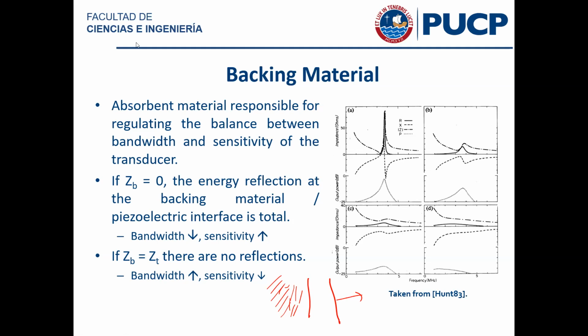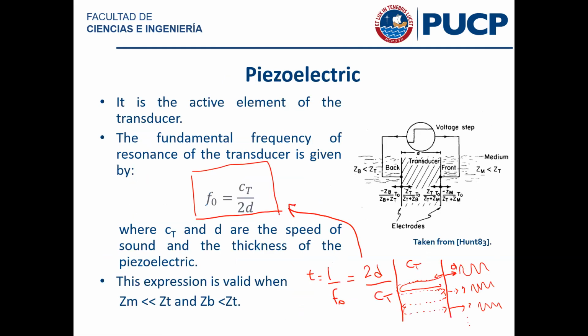So we have one question in here. So is this all happening inside the piezoelectric? So by all of this, I presume that you're referring to these multiple reflections, going back and forth and back and forth. Yes, this would be the piezoelectric element, that thing that's bounded by the brackets that I just drew. So over here, you will have tissues. And over here, the way that we're describing it right now, you will have air, right?